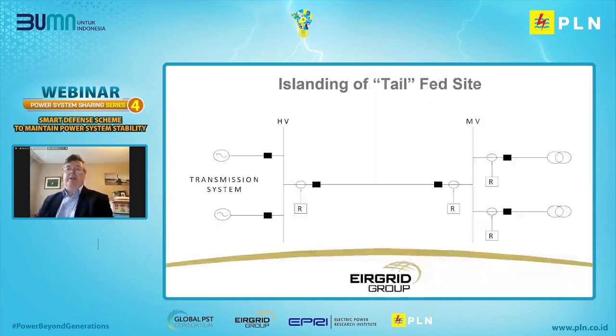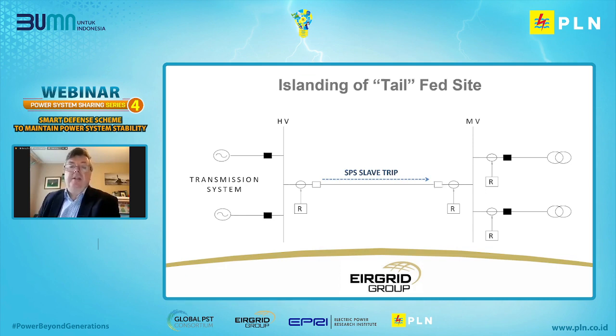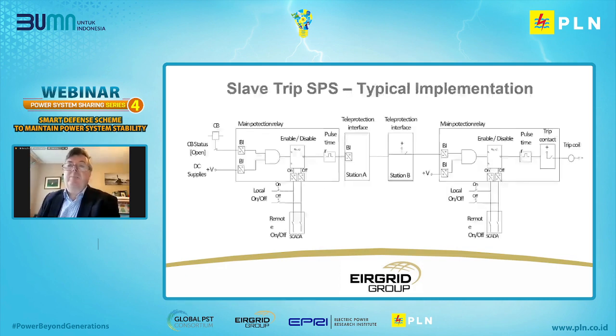So I suppose this, just advance one more, please. Yeah, so we're showing here, on the right-hand side, a piece of tail-fed network, and basically the breaker back at the source end of the line has opened. So basically, a slave trip is sent to the breaker at the remote end. So next slide, please. Yes, that slave trip basically opens the breaker.